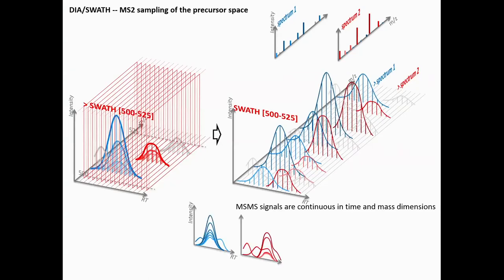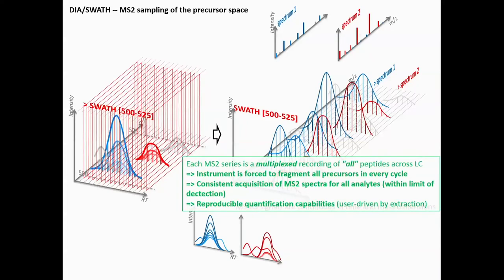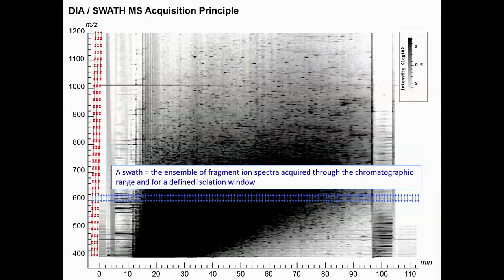If you know where to look and what the appropriate fragment ions are, you can still retrieve a specific signal — it ends up looking something like SRM data. The instrument is forced to fragment all precursors in every cycle, and we have consistent acquisition of MS2 spectra for all analytes within the limit of detection. We hope this will lead to reproducible quantification capabilities similar to what's available with SRM. Here we have the retention time and mass-to-charge dimensions, each dot is essentially a peptide, and we try to comprehensively sample this precursor space with windows of 25 mass-to-charge units. One SWATH is the ensemble of fragment ions and spectra collected over the whole retention time gradient for one precursor isolation window.